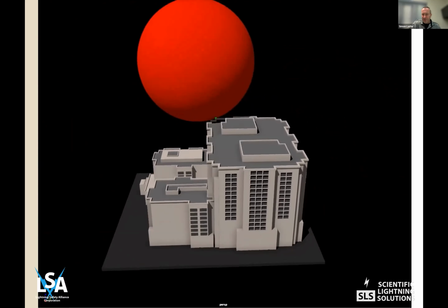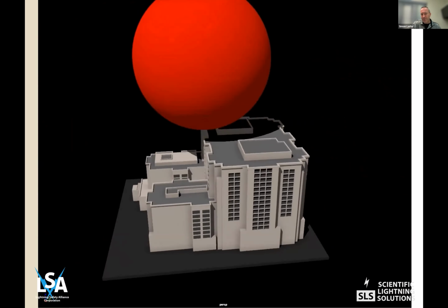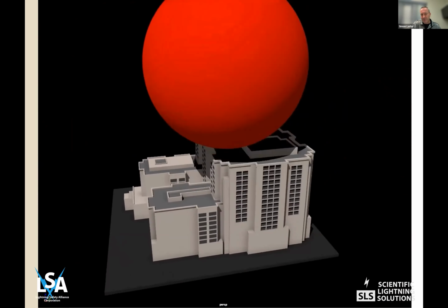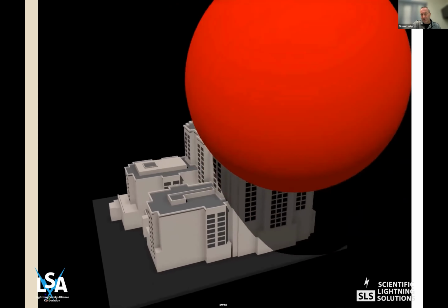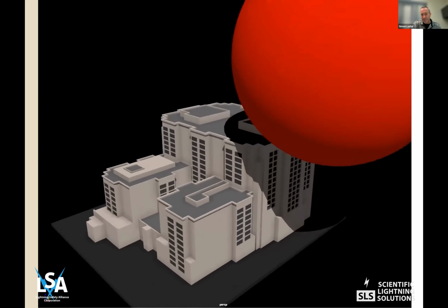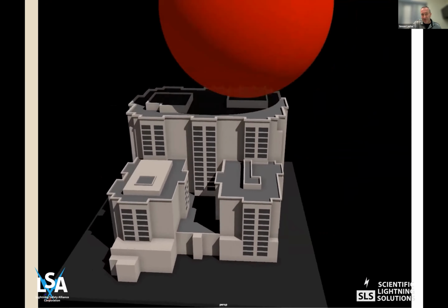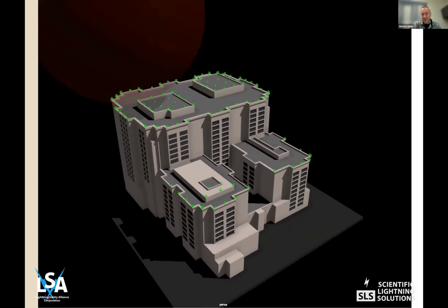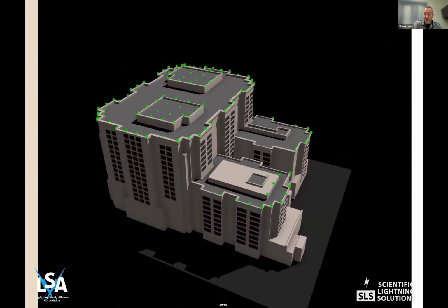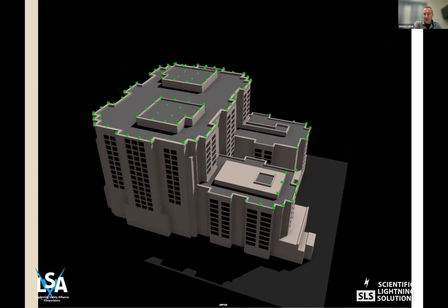So now we can consider this structure protected from lightning. I'll call your attention to those 2 penthouses. That sphere is rolling up and over them, but they are wide enough that the sphere was going to be hitting in the middle of those penthouses too. So that's a wide flat roof area. We can't ignore those. Even though the risk of counter leader development is lower on a wide flat roof area, it's not zero.